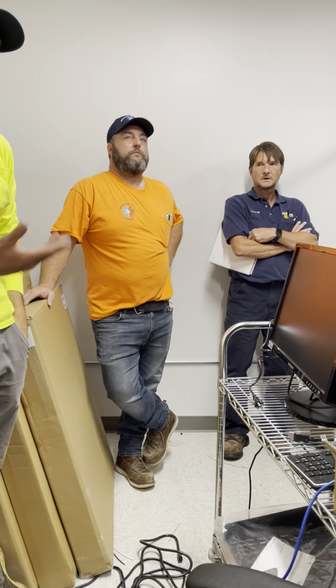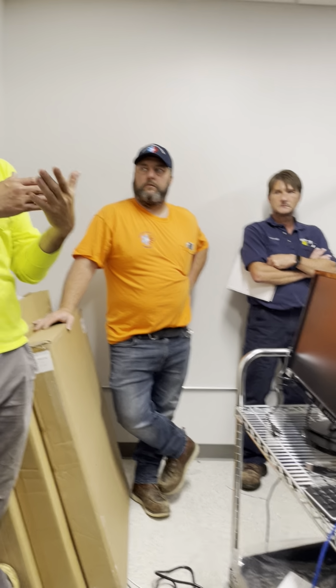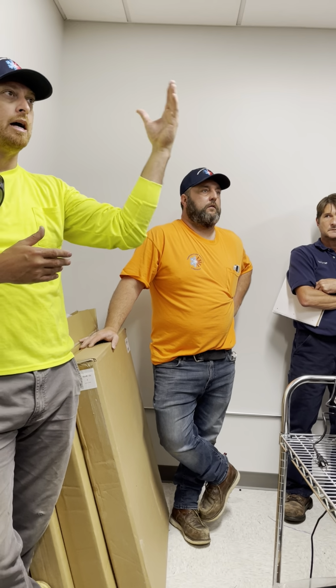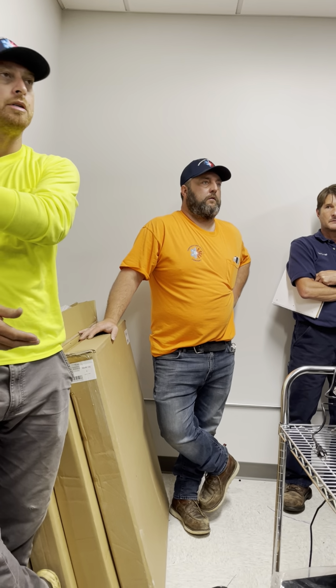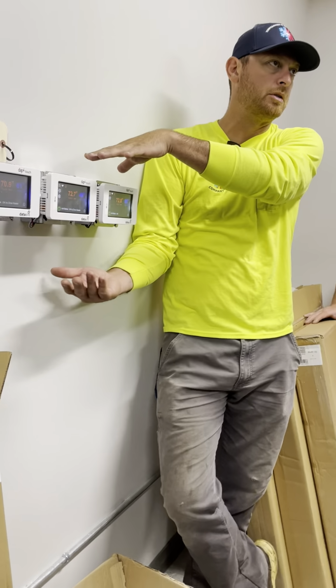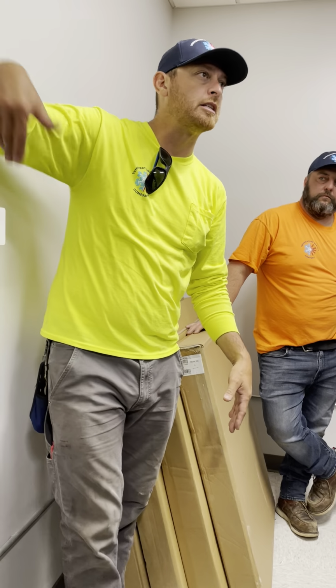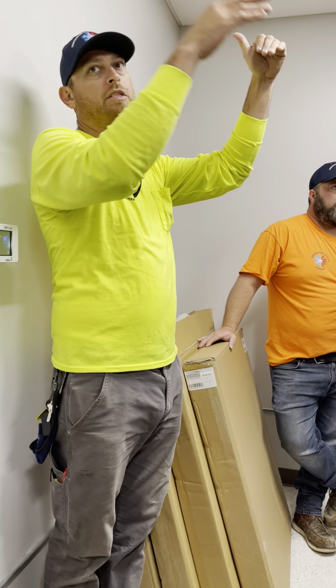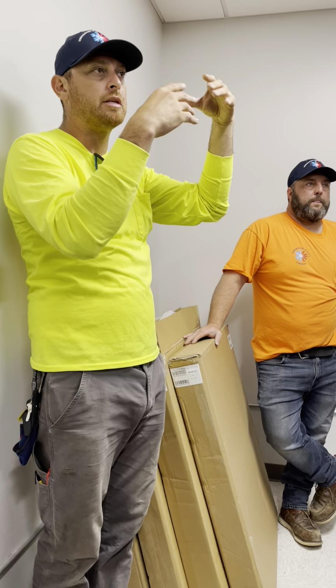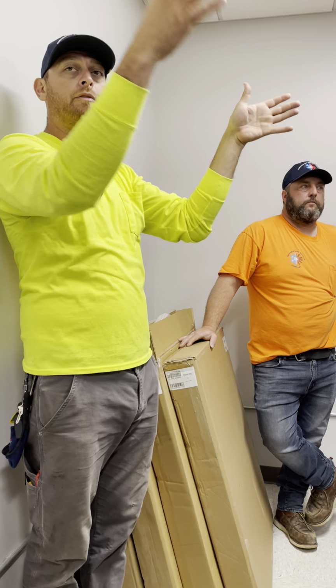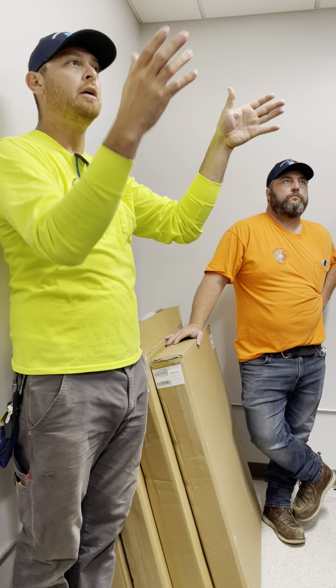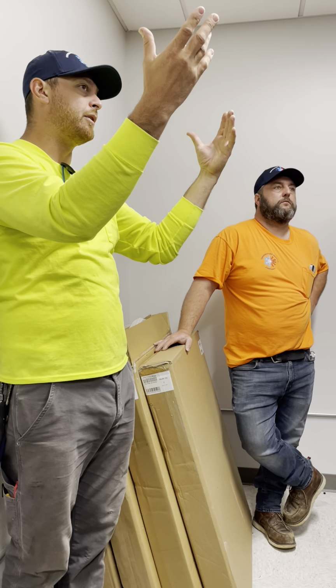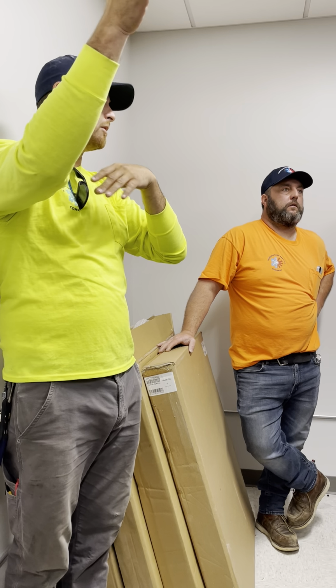Right now, since we're trying to figure out how we're going to communicate through the BAS comm lines, each has its own individual personal setting in here, almost its own personal BAS, everything's about 2 degrees off. So if one cycles in and can't keep up based on the temperature, because you do have different section areas of heat load in here, the other one will kind of make up for that time while it circulates later.